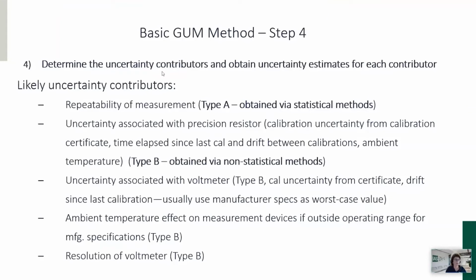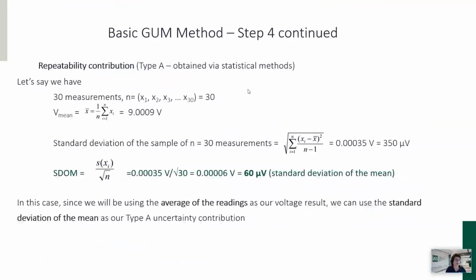So going through this, now let's go back to our example and see whether we can assign some contributors to this example. So let's start with our type A, where we obtain an uncertainty via statistical methods, meaning that we're taking multiple measurements. Let's say in this case we take 30 measurements, and that value that I used in the earlier calculation was the mean, or the average, of those 30 measurements.